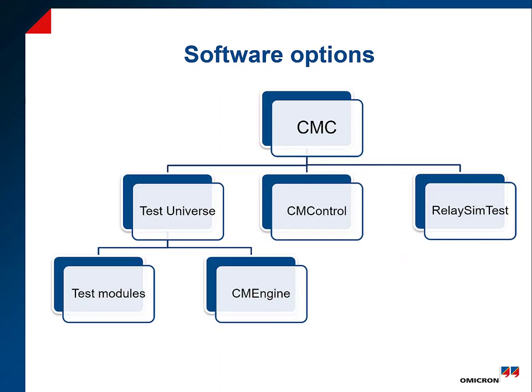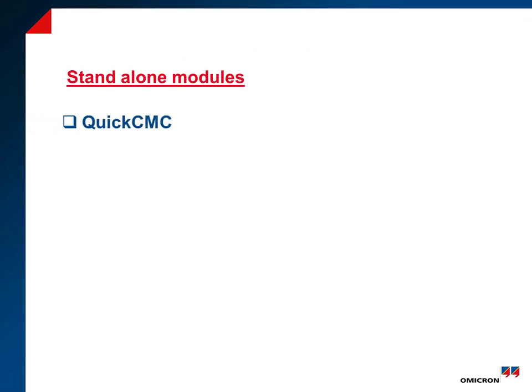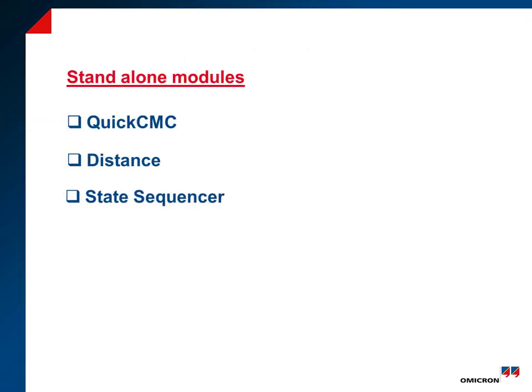There are different options for controlling the CMC test sets. Test Universe is a powerful software suite that comprises several modules, including general-purpose and dedicated modules for specific protection functions and applications. All of them are stand-alone, meaning they can run autonomously.